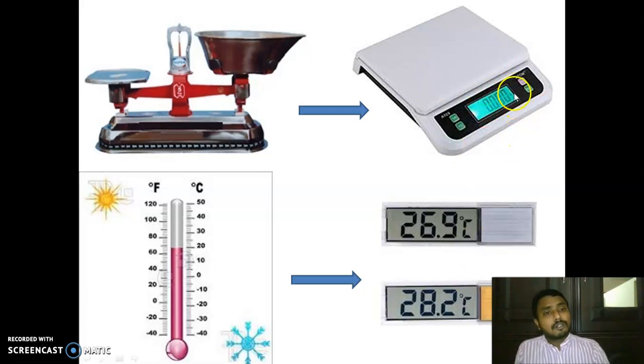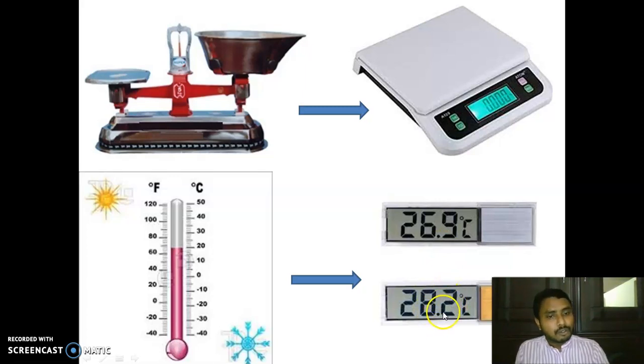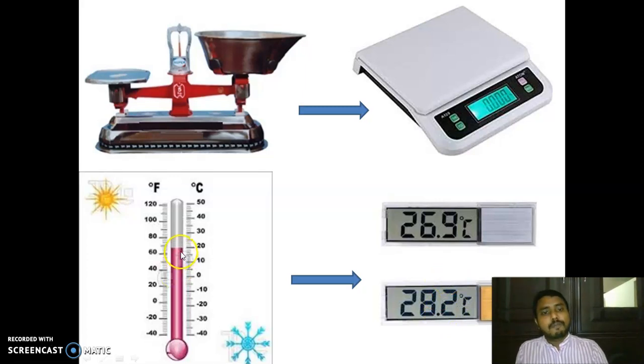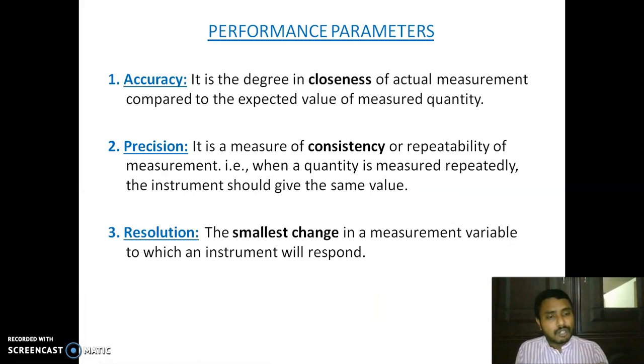For the thermometer, the next increment goes from 28.2 to 28.3, so the increment is 0.1 degrees. The resolution of this instrument is 0.1 degrees Celsius. Resolution means the smallest digit or the smallest value that can be indicated by the measuring instrument between two successive measurement steps.